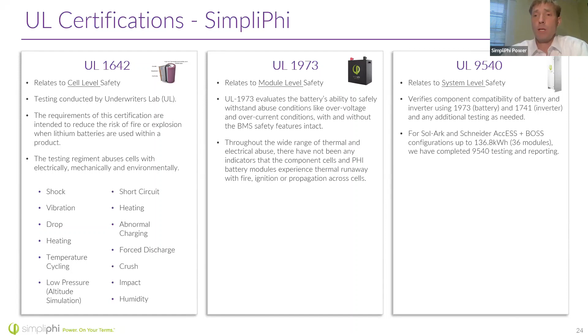So one more time, the UL 9540 is a whole system level test. It includes the inverter and the batteries, or the charge controller and the batteries. We have been certified with a number of different inverters like Schneider and Sol-Ark, etc. The 9540A, again, is just a test, not part of the certification. It's just a test to inform how to run the 9540 certification.